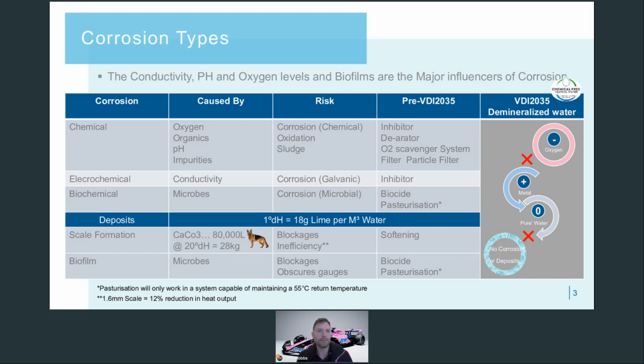Removal of oxygen, as you can see in pink in this diagram, is the first step to break the corrosion chain. Secondly, electrochemical corrosion is caused by conductivity, especially a problem where dissimilar metals are present and where there are minerals in the water. This is usually addressed with chemical inhibitors, but instead, simply demineralizing the water eliminates the conductivity. If you remember those dissolved minerals with differing electrical charges from the last slide, they're gone, and so the corrosion is stopped.